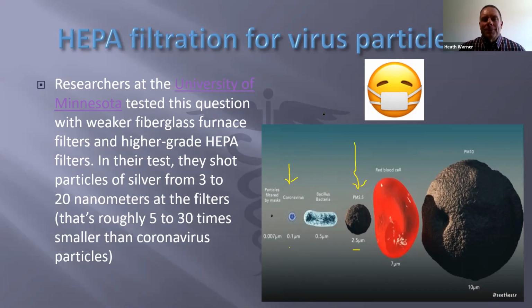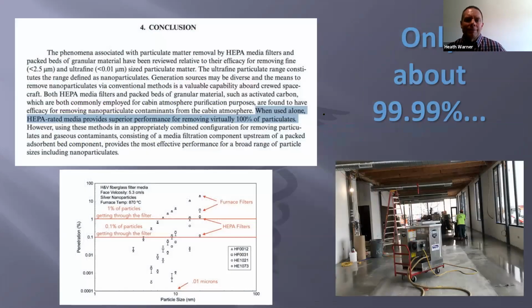But back to HEPA filtration. In the University of Minnesota study, they took silver particles between 3 and 20 nanometers, so 5 to 30 times smaller than a coronavirus particle, and shot them through HEPA filtration. The result of the test, and emphasis was mine, sorry, the result of the test: it's 99.9%, it's 100%. Effectively, when they call it a HEPA scrubber, they're not kidding.